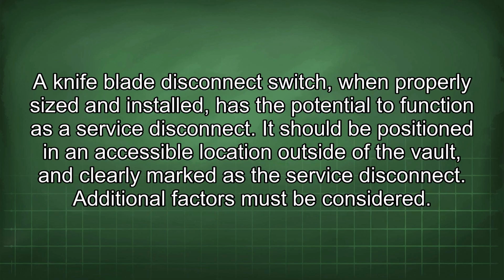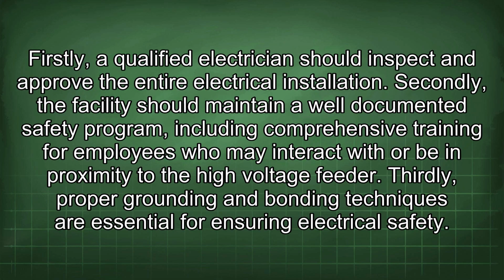A knife blade disconnect switch, when properly sized and installed, has the potential to function as a service disconnect. It should be positioned in an accessible location outside of the vault and clearly marked as the service disconnect. Additional factors must be considered. Firstly, a qualified electrician should inspect and approve the entire electrical installation. Secondly, the facility should maintain a well-documented safety program, including comprehensive training for employees who may interact with or be in proximity to the high-voltage feeder.